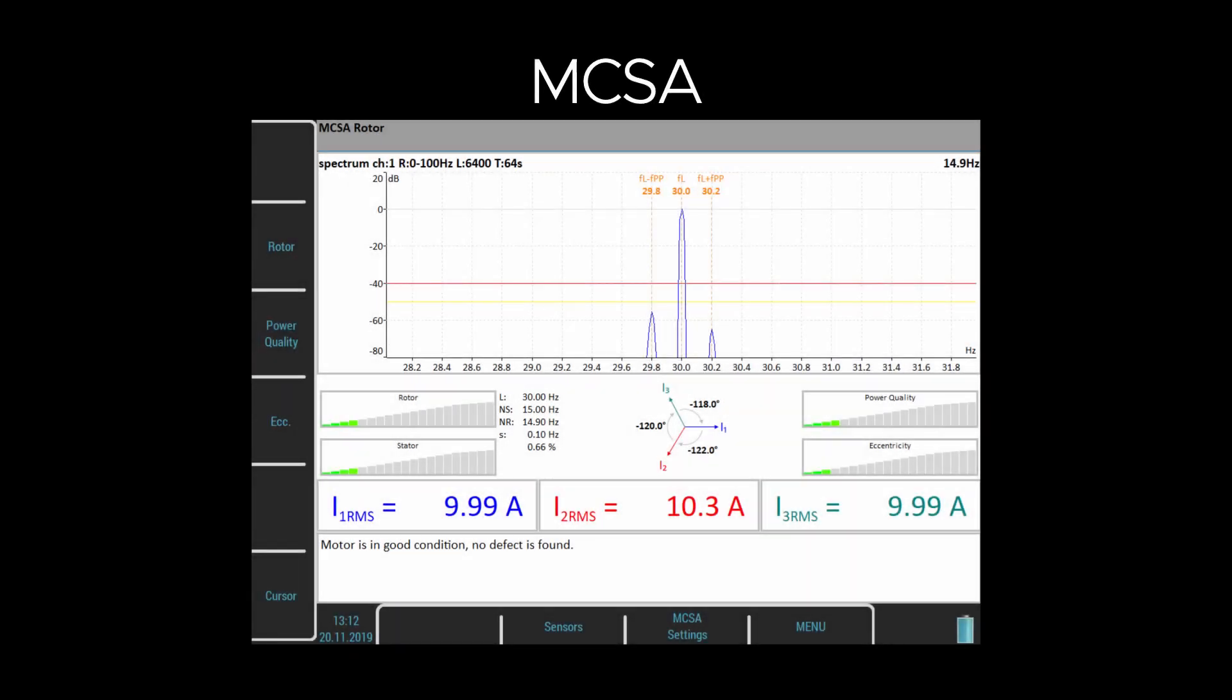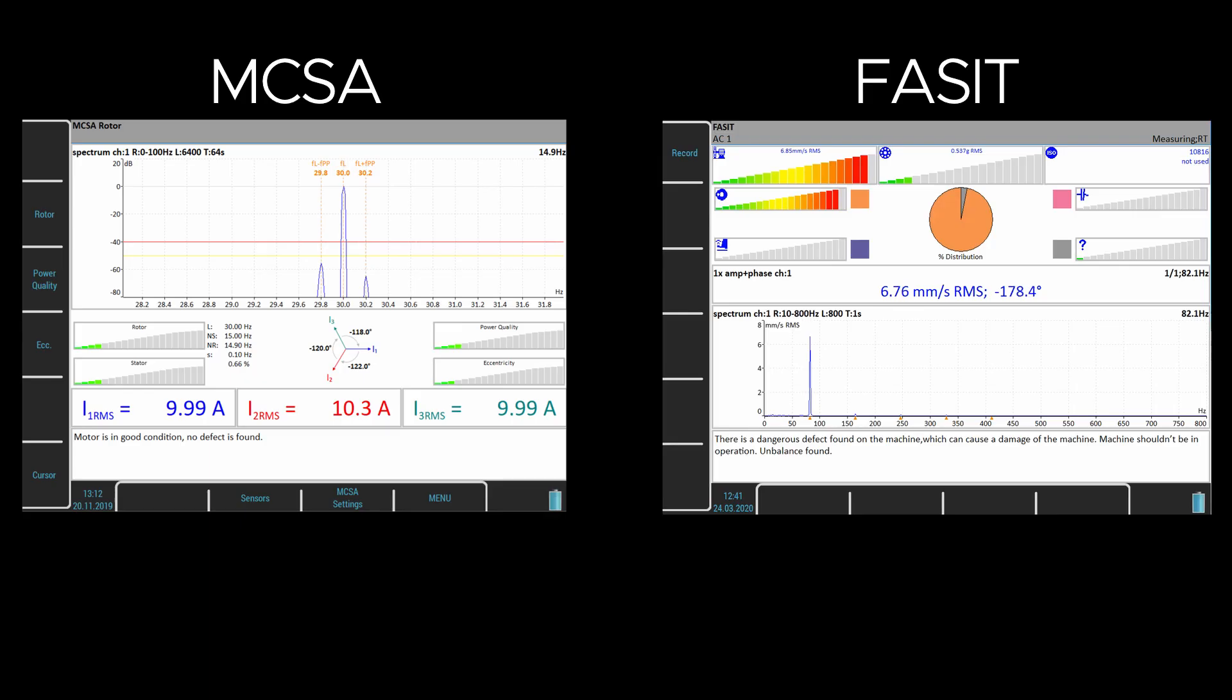Or you can use the automatic detection function. It is a similar feature to the ADASH automatic fault source identification tool FASIT for vibration analysis. The device can automatically recognize the main causes of failures such as unbalance, looseness, misalignment and bearing faults.